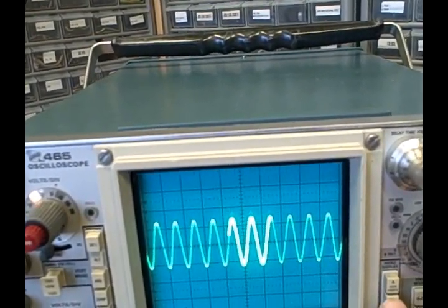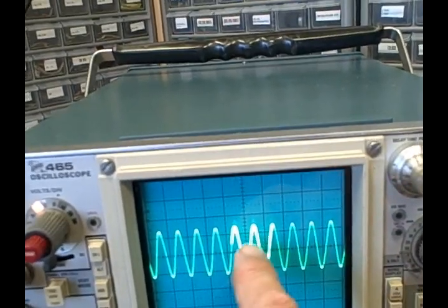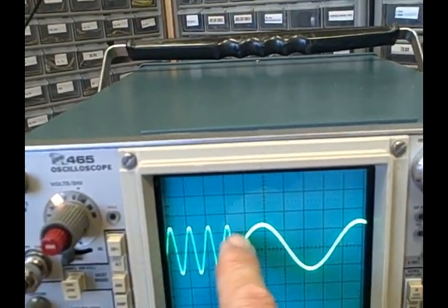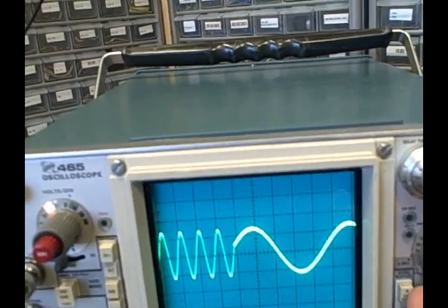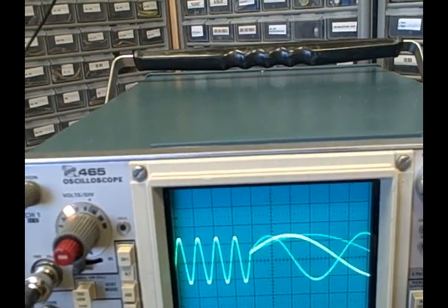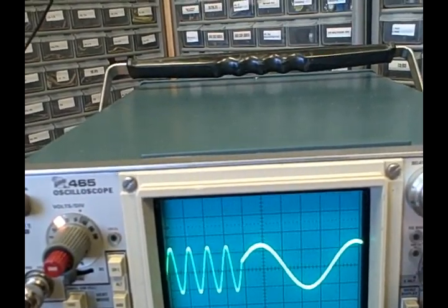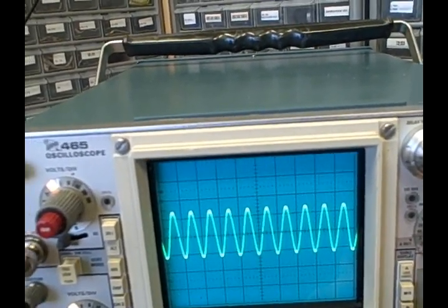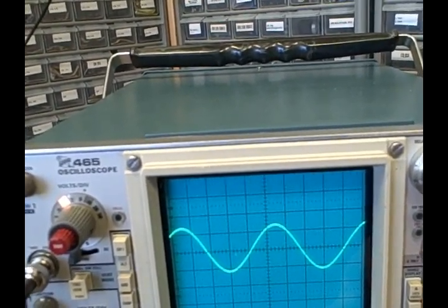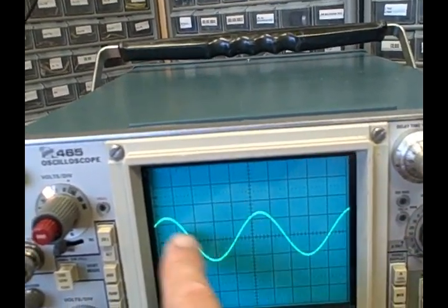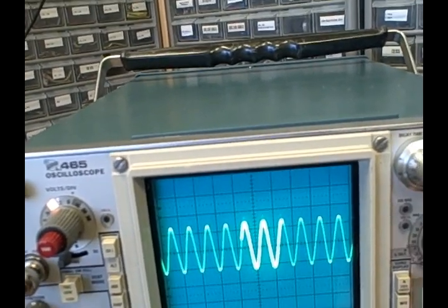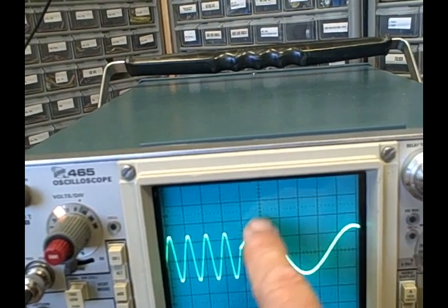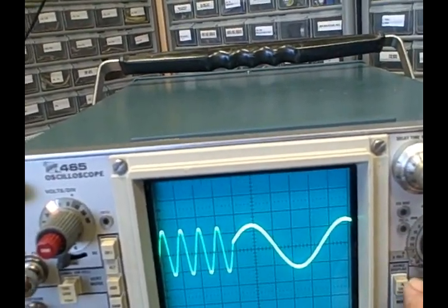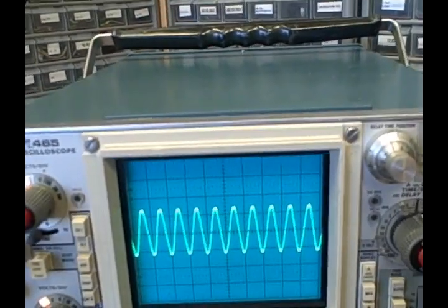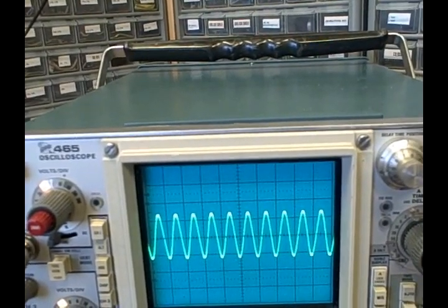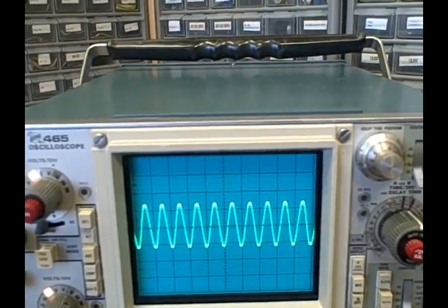Well, I can now punch in the mixed button, which lets me look at the original time base and then the new time base, which is a little bit faster. And I see 1, 2, 3, 4, and then all of a sudden I see expanded the portion of the wave. Now I can change the amount of expansion, make it more, make it less. But it will always be a little more expanded than the normal wave. And if I just want to take a look at the expanded waveform, then I can hit B delayed, and that'll show me only the expanded portion of the waveform. So here's the area I'm looking at that's B intensified. Mixed gives me the original, then after the time delay takes off with the expanded waveform, and then back to the normal. So that's the time delay portion of the unit and what it does for you.